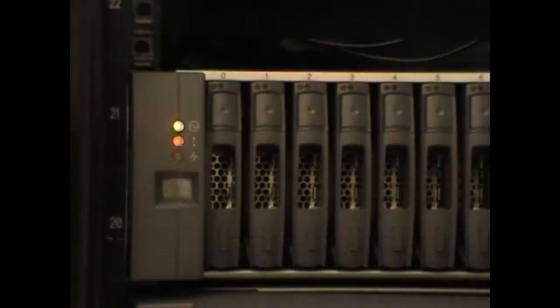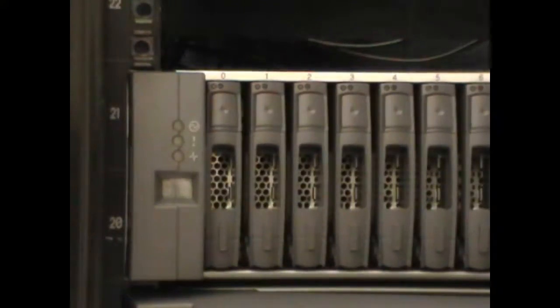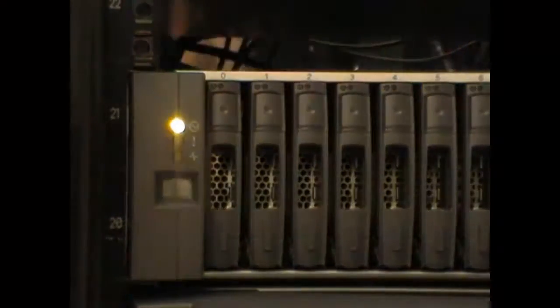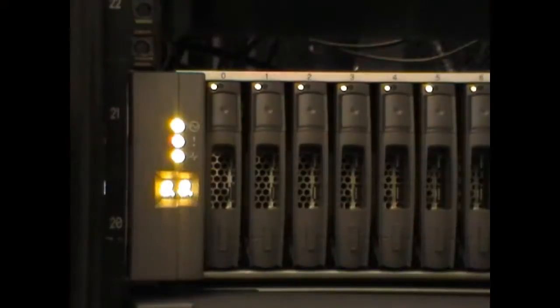The final step is to turn the shelf off and then back on again. If the shelf ID remains blinking, then the ID has not been set, and Data ONTAP will use the shelf serial number to indicate a shelf problem. In this case, the ID has taken.